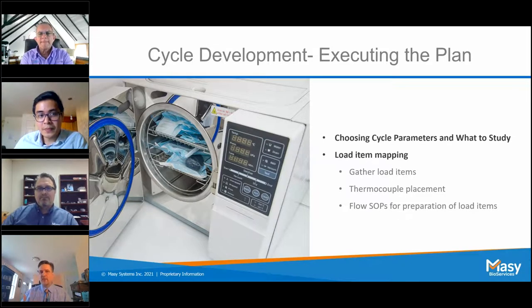And what we recommend doing is placing at least 2 sensors, 2 thermocouples inside each load item when we're doing cycle development and the heat studies, to be able to determine where the worst case spots within those load items are. So at least 2, sometimes it's more than that, but that data will get used during PQ because that's where we'll place our thermocouple and our BIs at that point. So those are key. Document everything again, that's huge.